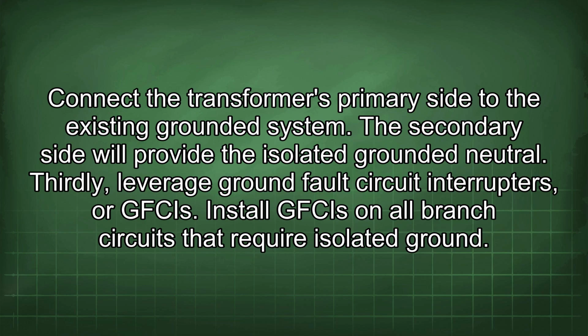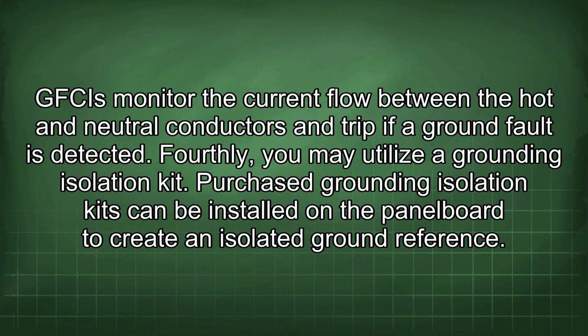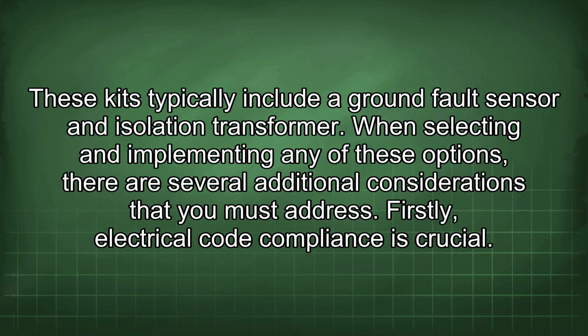Thirdly, leverage ground fault circuit interrupters, or GFCIs. Install GFCIs on all branch circuits that require isolated ground. GFCIs monitor the current flow between the hot and neutral conductors and trip if a ground fault is detected. Fourthly, you may utilize a grounding isolation kit. Purchased grounding isolation kits can be installed on the panel board to create an isolated ground reference. These kits typically include a ground fault sensor and isolation transformer.